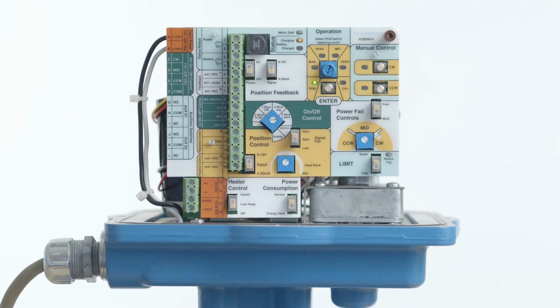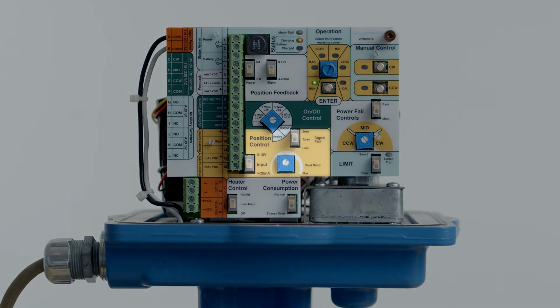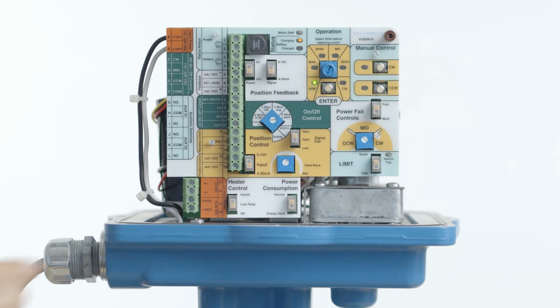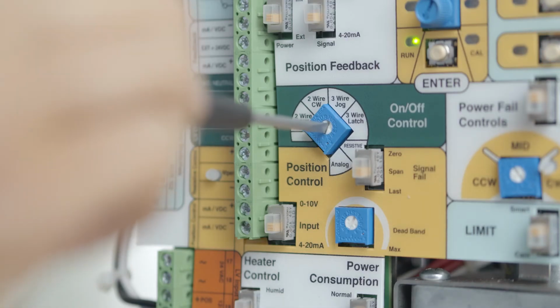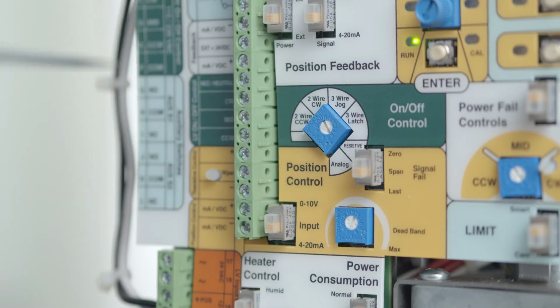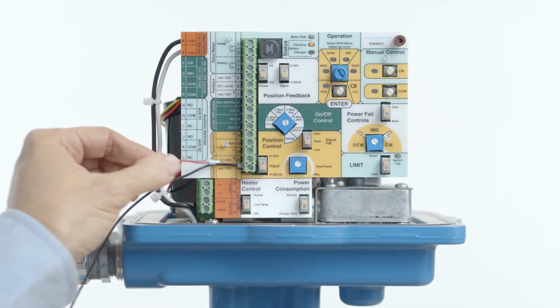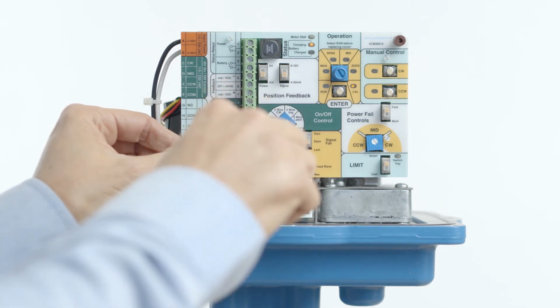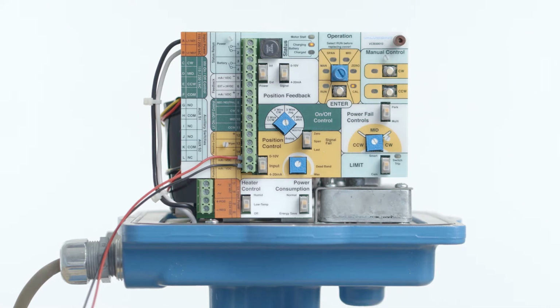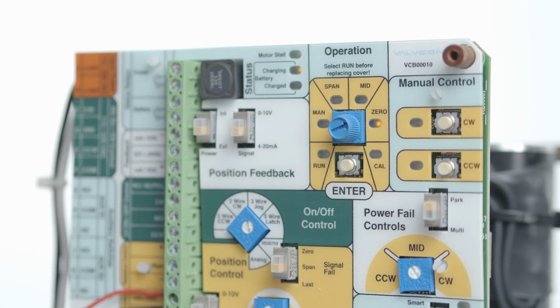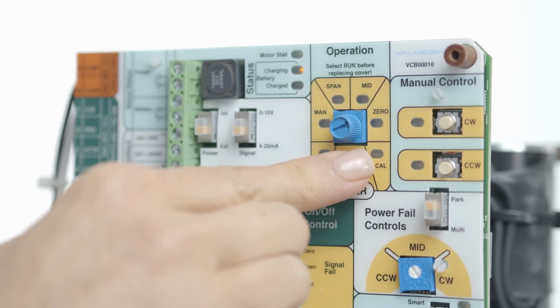and span positions. To control the actuator with a 4 to 20 milliamps or 0 to 10 volts DC analog signal, first, slide the input switch up to select 0 to 10 volts or down to select 4 to 20 milliamps. Select analog in the position control region of the mode selector. Then connect milliamps or volts DC positive to terminal 15 and the milliamps or volts DC negative to terminal 16 on the universal control board. Turn the mode selector dial to 0 and press Enter for 2 seconds. The 0 LED will begin to flash.